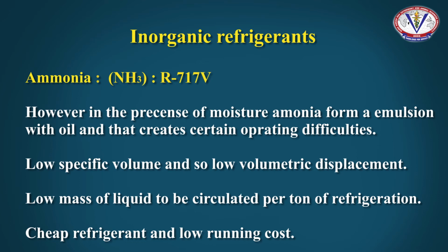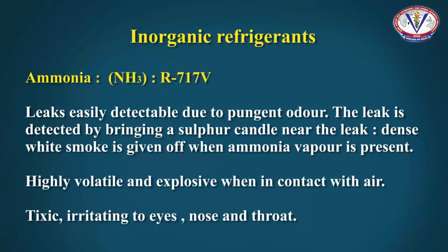Low specific volume and low volumetric displacement, low mass of liquid to be circulated per ton of refrigeration, cheap refrigerant, and low running cost. Leaks are easily detectable due to pungent odor. The leak is detected by bringing a sulfur candle near the leak. Dense white smoke is given off when ammonia vapor is present. Highly volatile and explosive when in contact with air. It's toxic, irritating to eyes, nose and throat.